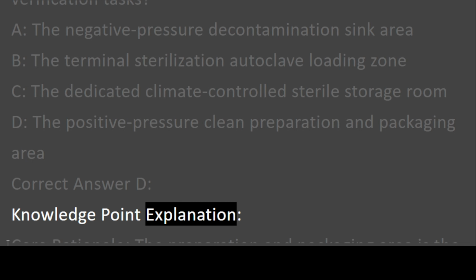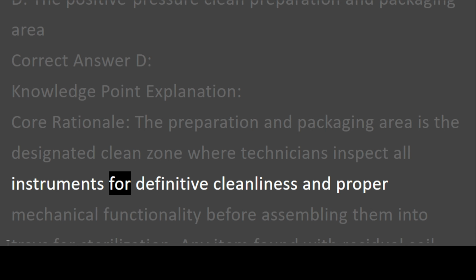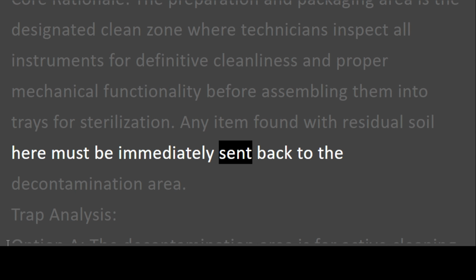Correct answer D. Knowledge point explanation. Core rationale. The preparation and packaging area is the designated clean zone where technicians inspect all instruments for definitive cleanliness and proper mechanical functionality before assembling them into trays for sterilization. Any item found with residual soil here must be immediately sent back to the decontamination area.